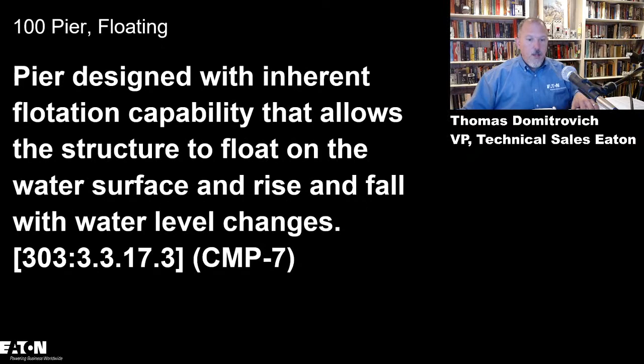In land areas, Article 100 talks about electric datum plane distances. The electrical datum plane shall consist of one of the following: in land areas subjected to tidal fluctuations, it shall be a horizontal plane 2 feet above the highest tide level for the area occurring under normal circumstances. So you're looking at tide levels and flood levels -- the highest water level for the area under normal circumstances, 2 feet above that. What is that number? What is that water level under normal circumstances?